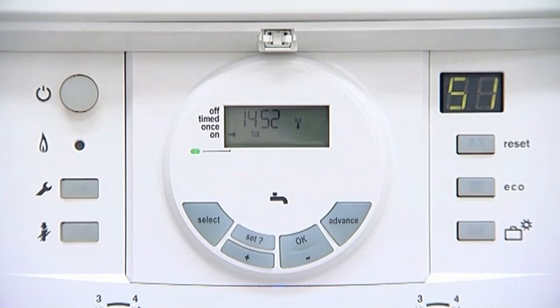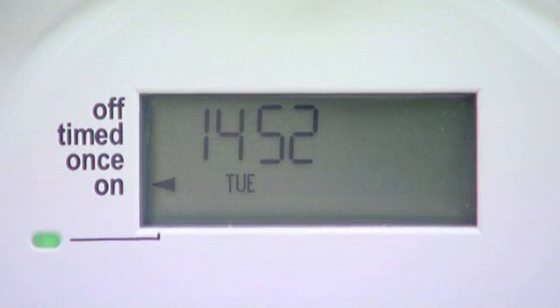If your heating is not working as expected, it could be that your radio frequency thermostat has lost its signal with the receiver. The batteries are low on power, or there has been a power cut, indicated by the CH and the antenna symbol flashing on the boiler receiving panel.